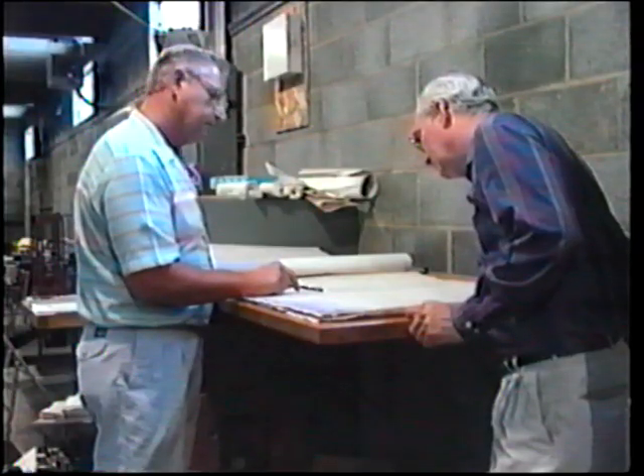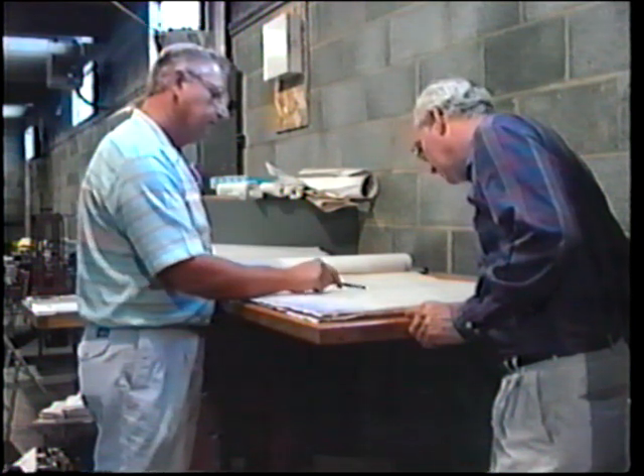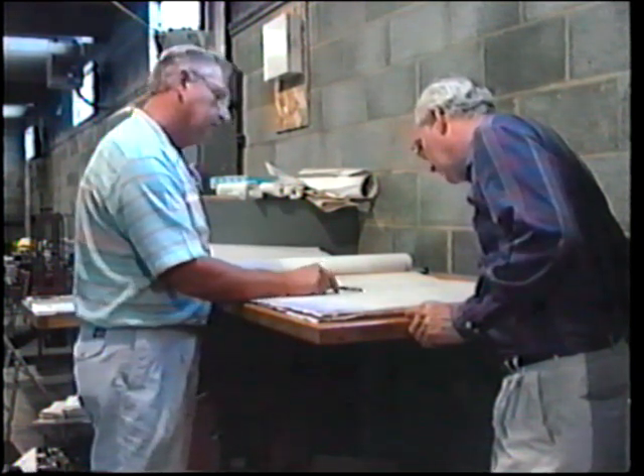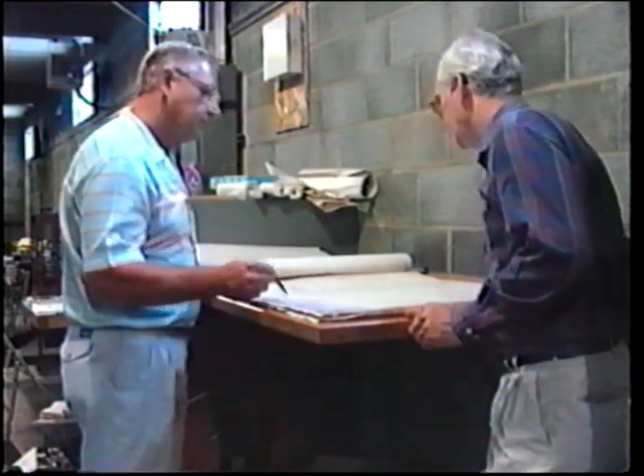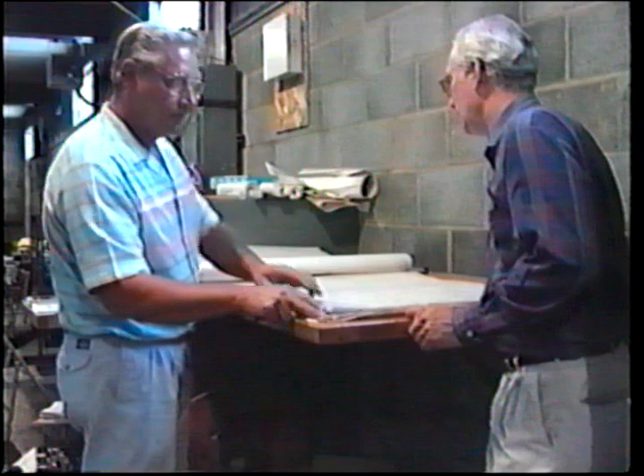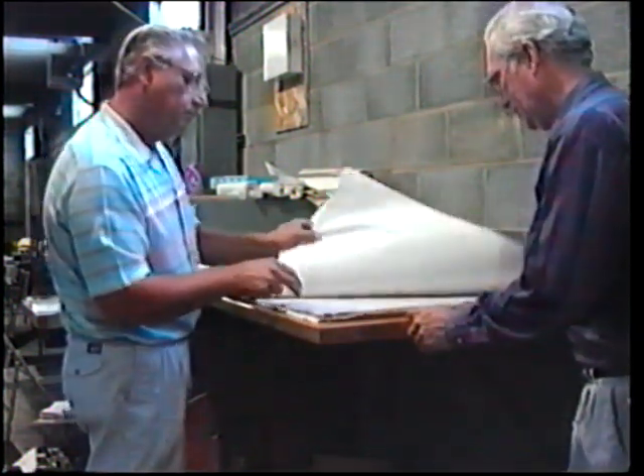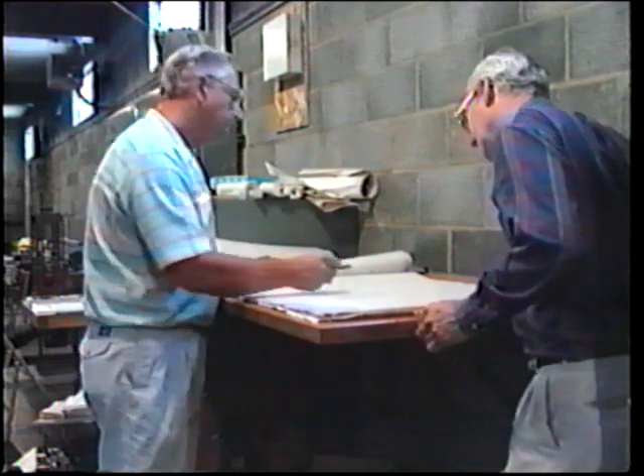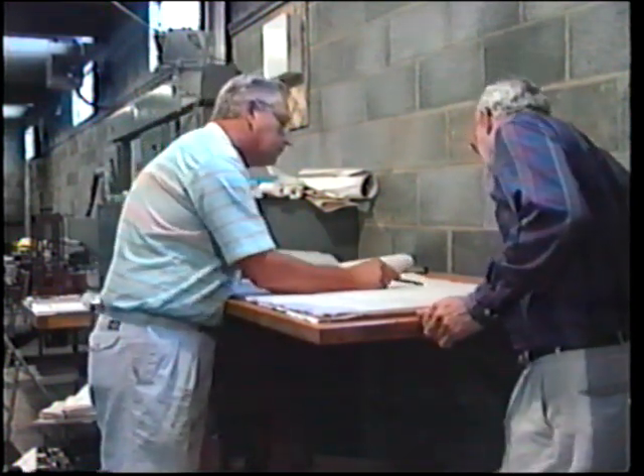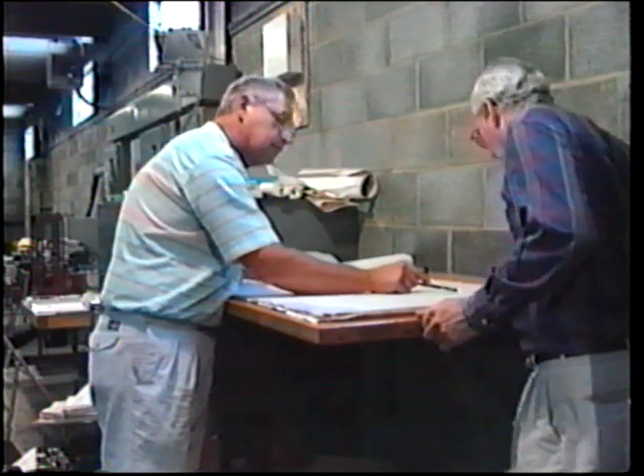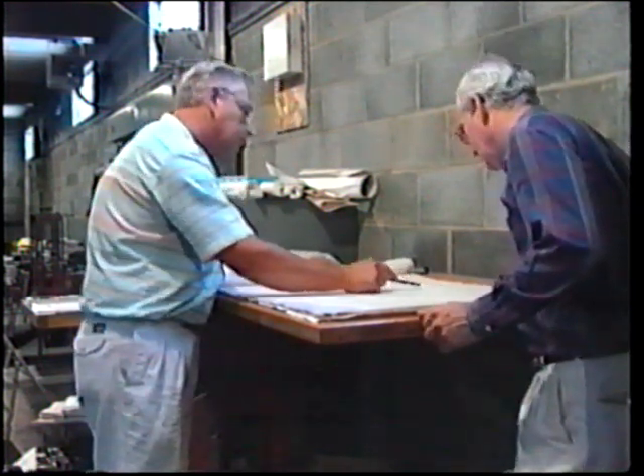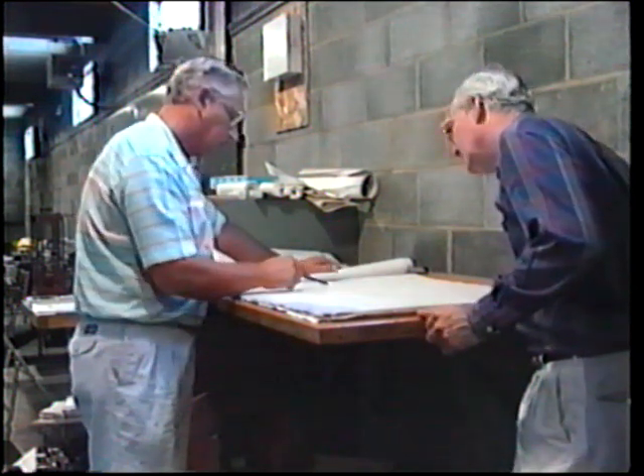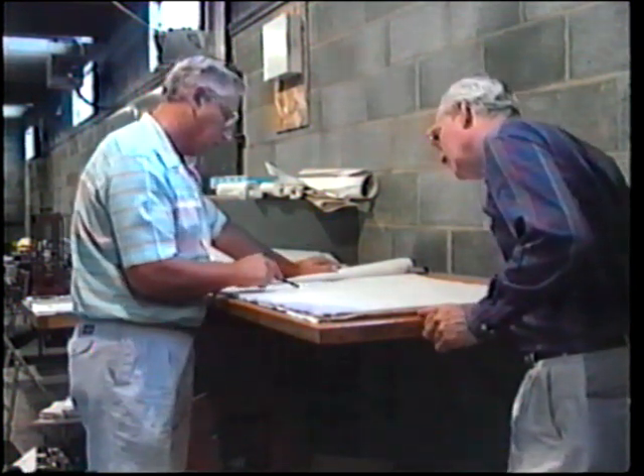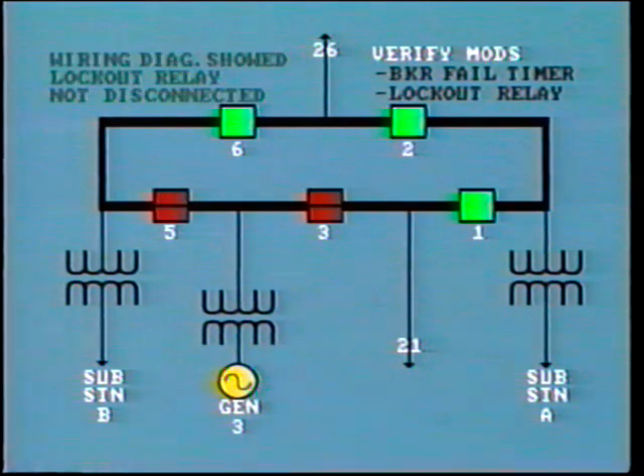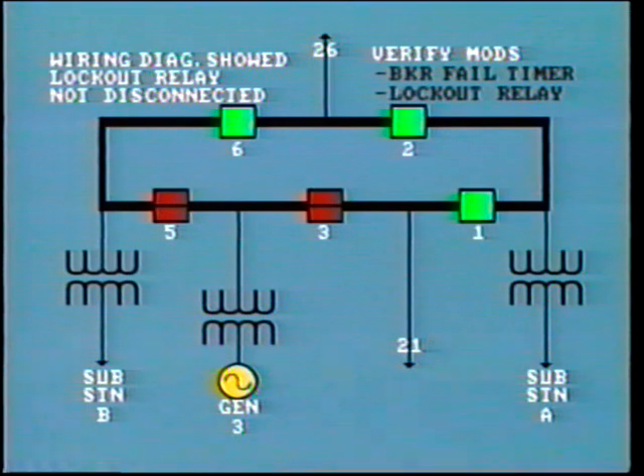When they reviewed the construction schematics, this did indeed indicate that both lockouts were out of service with their output wiring disconnected. These schematics were actually drawn to show the eventual final circuitry after modification. Just to make another check, they looked at the physical wiring diagrams for the panel. But by this time, they had already convinced themselves that both lockout relays were out of service. In fact, they failed to recognize that the wiring diagrams actually showed the physical location of each lockout relay. It also indicated that the lockout for breaker number 6 was not yet disconnected. Presumably, this would be carried out at a future operation.